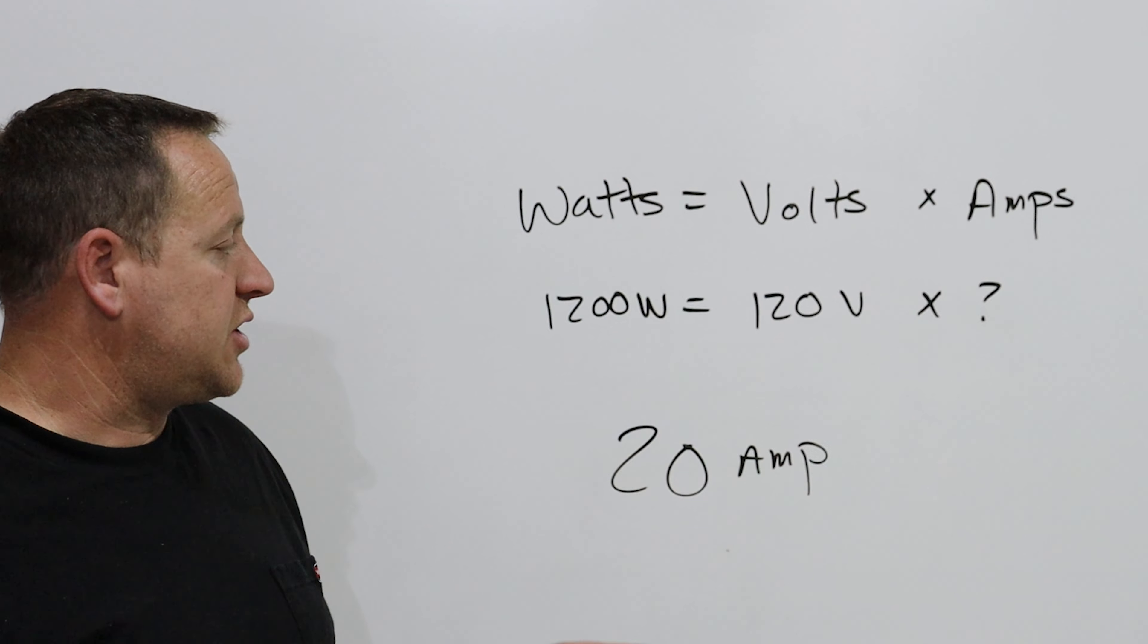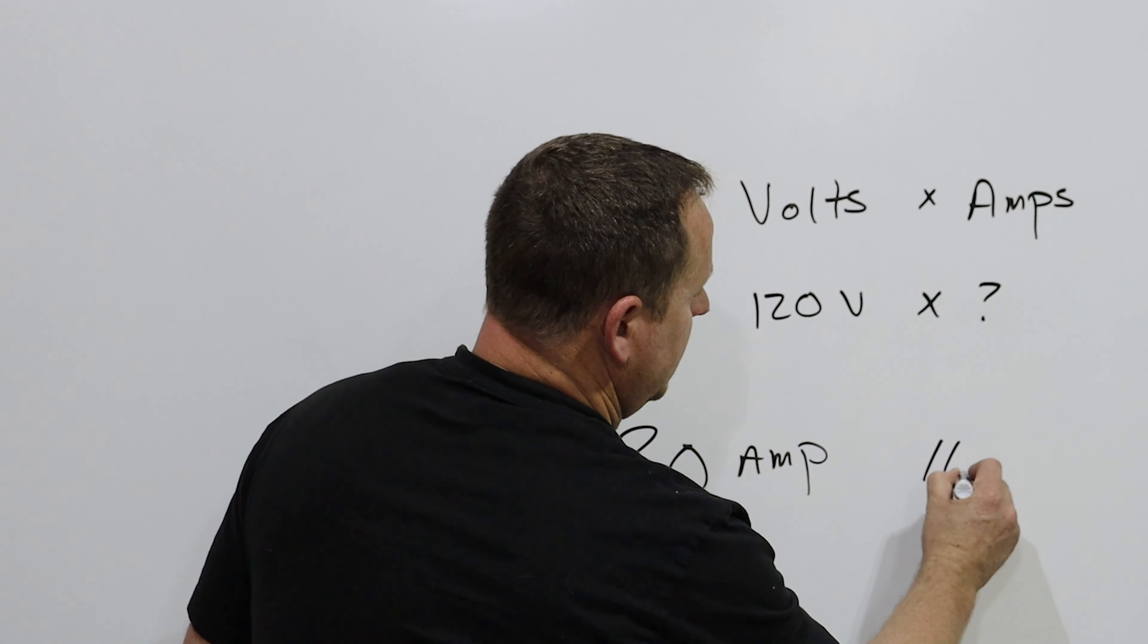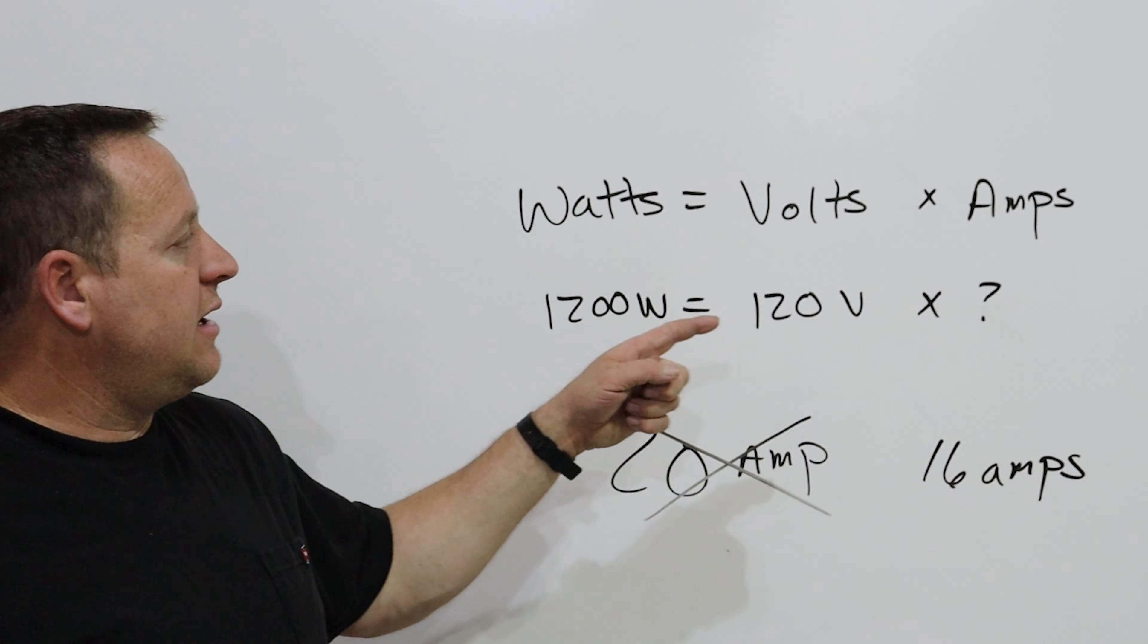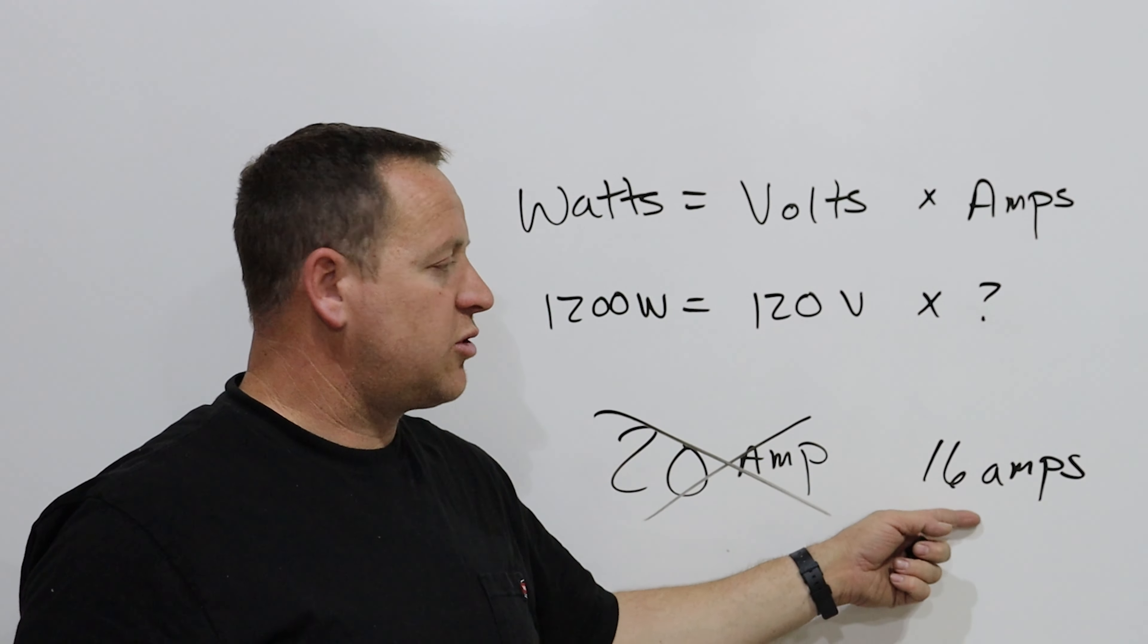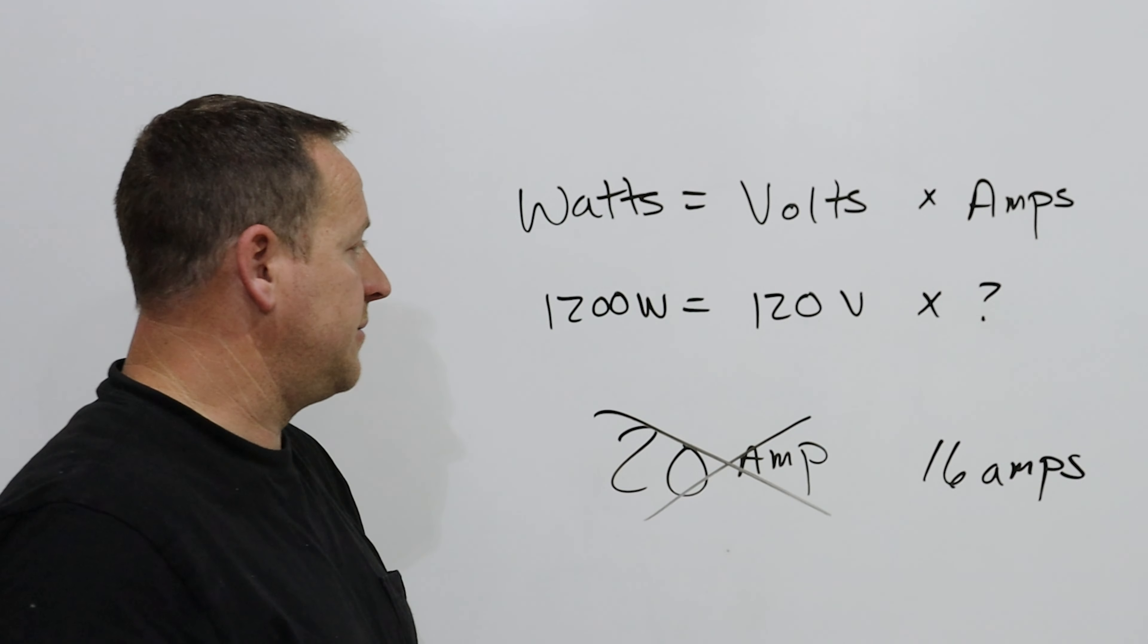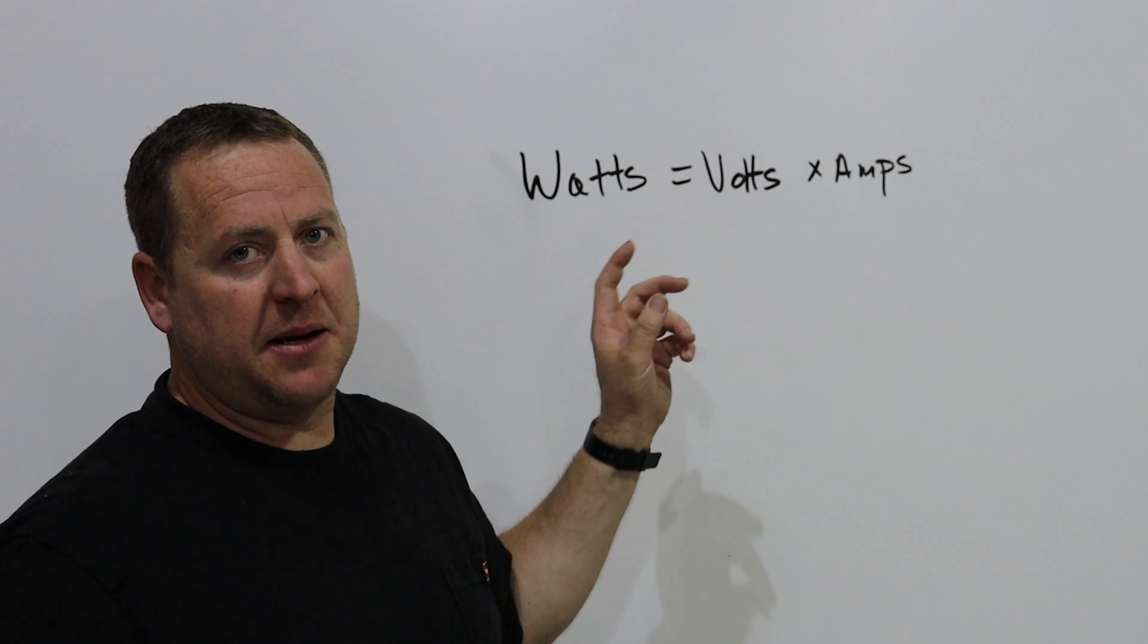With a 20 amp circuit, it's generally going to trip your breaker somewhere around 16 amps. So really you want to be figuring on what you can run and get somewhere up to about 16 amps, which is 80% of the capacity of the circuit.